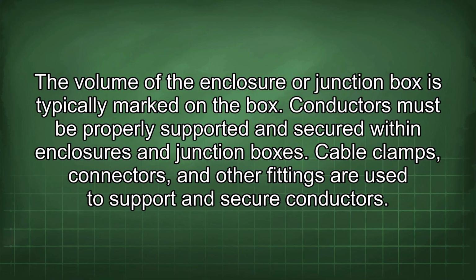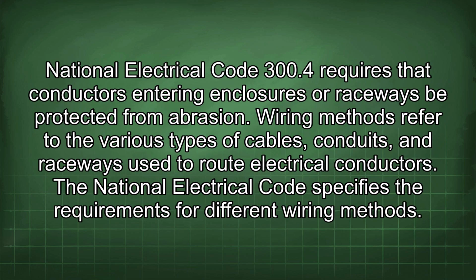Conductors must be properly supported and secured within enclosures and junction boxes. Cable clamps, connectors, and other fittings are used to support and secure conductors. National Electrical Code 300.4 requires that conductors entering enclosures or raceways be protected from abrasion. Wiring methods refer to the various types of cables, conduits, and raceways used to route electrical conductors. The National Electrical Code specifies the requirements for different wiring methods.